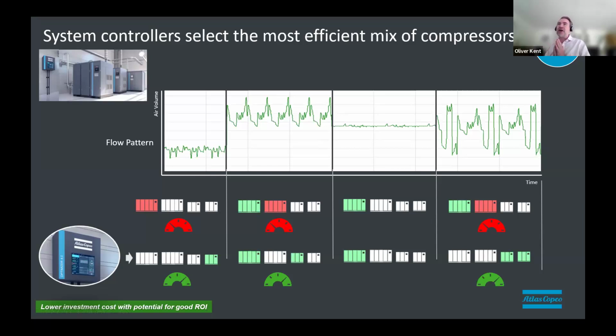That's why on virtually every compressor system with more than one compressor, you really want to think about investing in a system controller. When we look at efficiency, we're looking at compressor design, at whether we can save 1% here and 1% there by fine-tuning our compressor designs to make them as efficient as possible. But control also plays a huge part in making our compressed air system run as efficiently as possible.